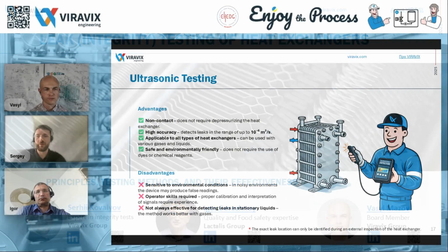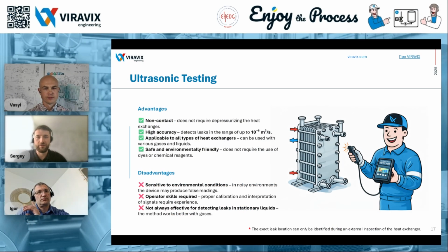Let's move on to the next testing method, ultrasonic testing. The principle of this method is that excess pressure is created inside the heat exchanger when checking for gas leaks, or a vacuum is created when searching for micro cracks on the casing. To detect leaks, an ultrasonic leak detector is used, also known as an acoustic detector. The operator directs the sensor toward potential leak locations such as joints, seals, and welds.